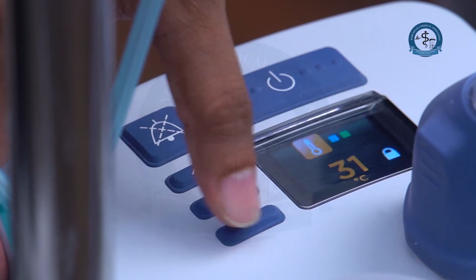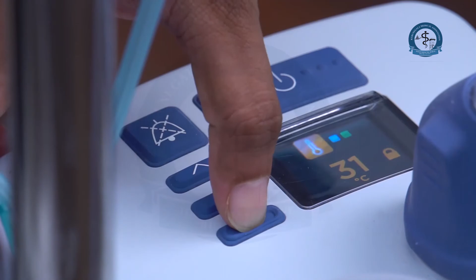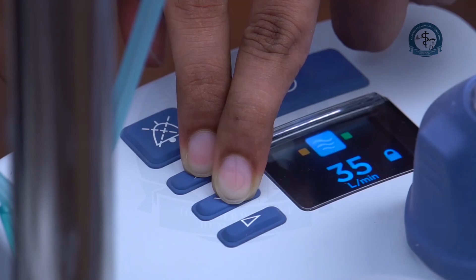The next setting is the flow. Here also, same as before, just press the up and down buttons together for a few seconds. Then the flow value will start blinking. Then adjust the flow rate using the up and down buttons. Once you get the desired value, confirm it by pressing the forward button. We can adjust the flow from 2 liters per minute to 60 liters per minute.